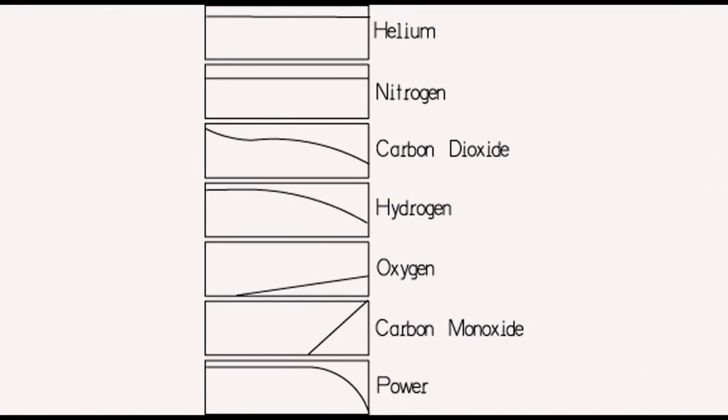In one of those scholarly research papers I came across, I discovered the holy grail I'd been searching for. It was a beautifully simplistic diagram showing how and why a sealed laser tube fails, basically confirmation of all the things I'd been working towards in part one. I'm going to reproduce the essence of that diagram here, but obviously I can't reproduce the real diagram by reason of copyright. If you're interested in tracking down the source of that scholarly work, I'll happily pass the link on if you message me on YouTube.